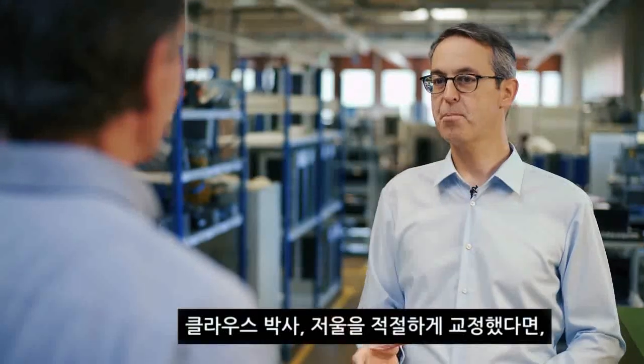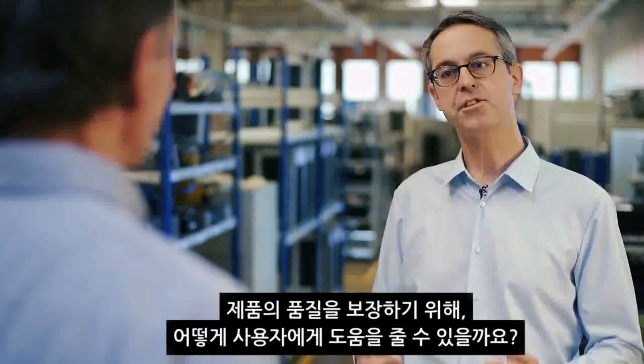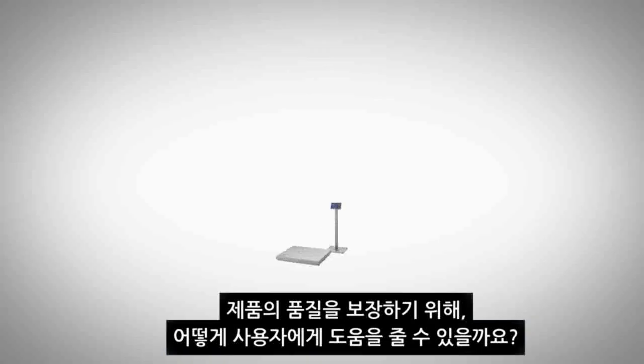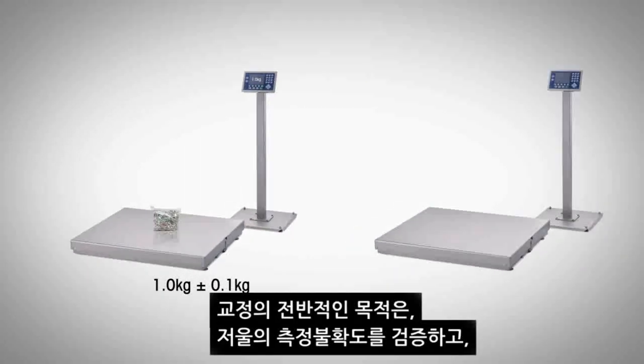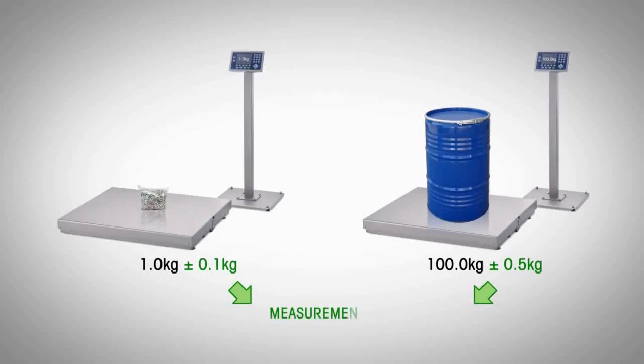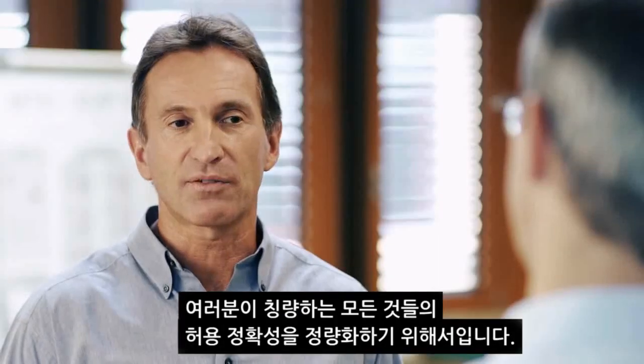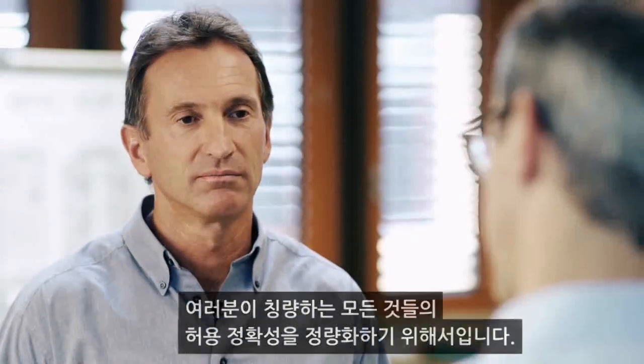Klaus, once a proper calibration has been performed, how does it help the user to guarantee good product quality? The overall purpose of calibration is to determine the measurement uncertainty of the device, and that allows you to quantify the accuracy of everything you weigh.